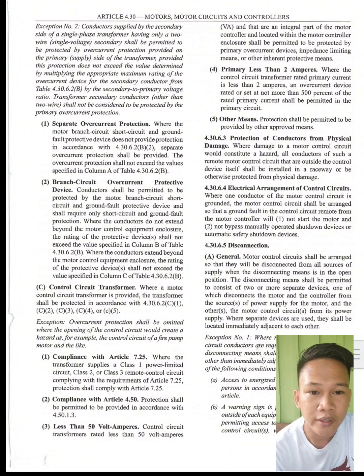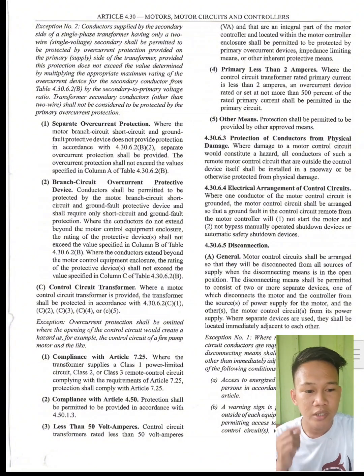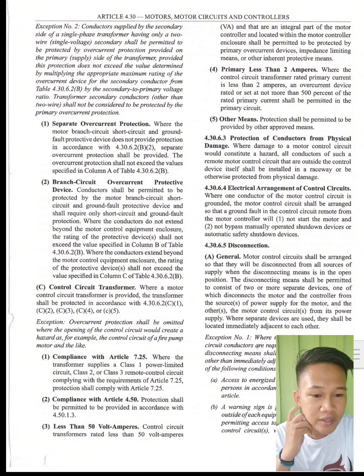So next is 4.30.6.4 electrical arrangement of control circuits. Where one conductor of the motor and control circuit is grounded, the motor control circuit shall be arranged so that a ground fault in the control circuit remote from the motor controller will, first, not start the motor. Second, not bypass manually operated shutdown devices or automatic safety shutdown devices.